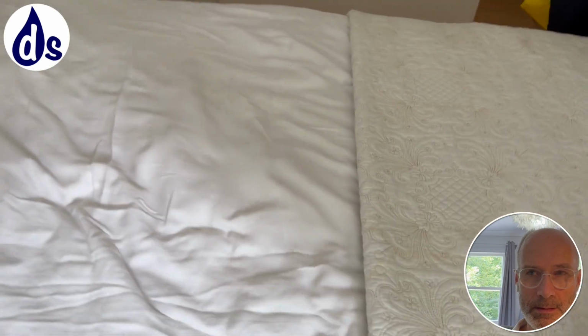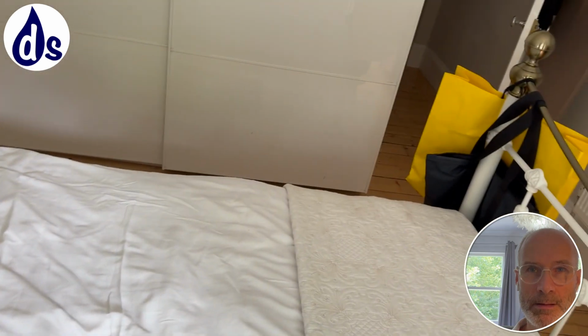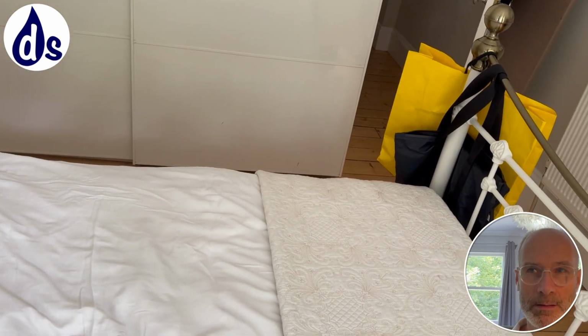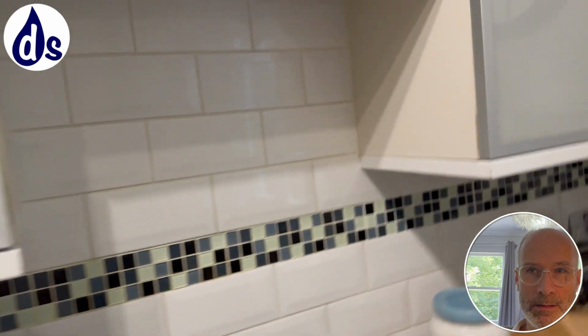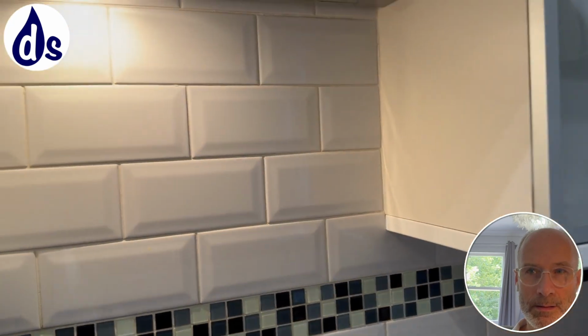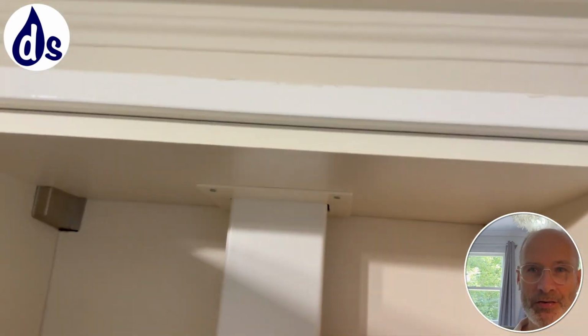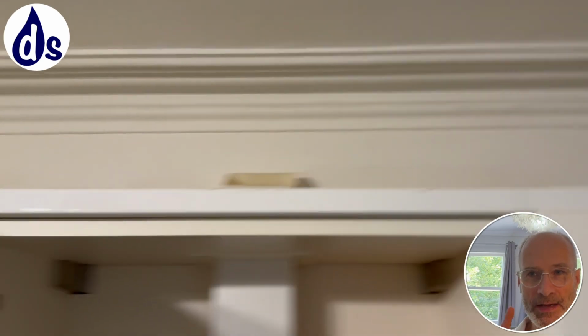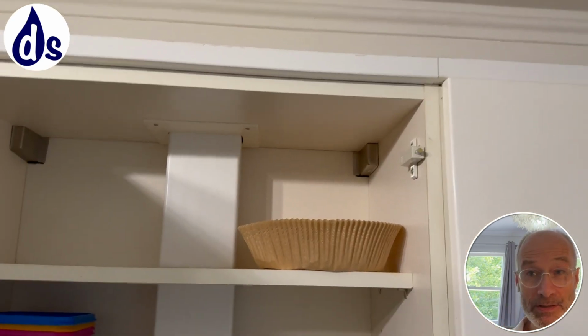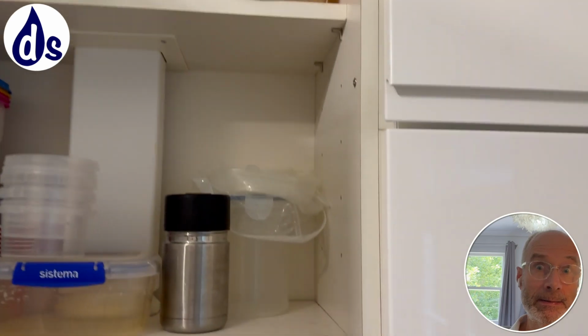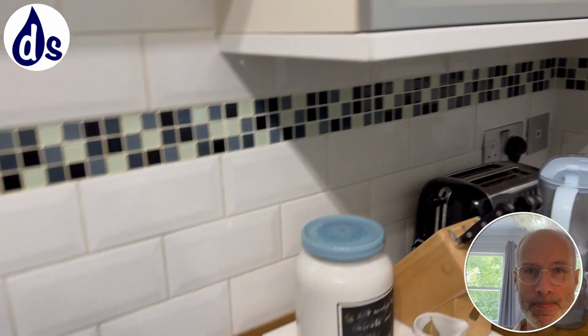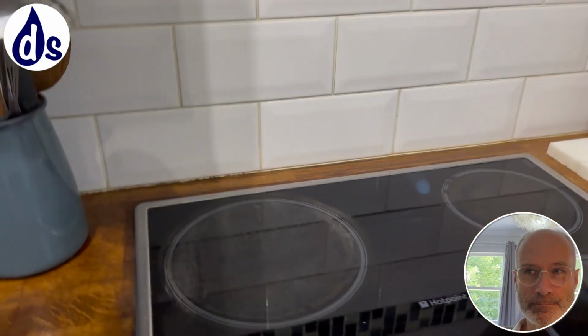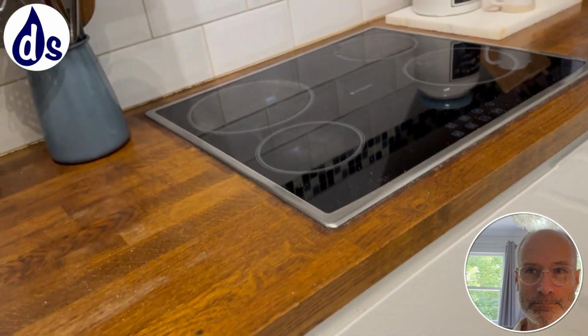So I'm going to measure the airflow from the bathroom with an air monitor. The kitchen extractor fan doesn't go out. When you pull this out, it's very common in the UK for kitchen extractor fans not to be externally ducted. Since 2012, it was a building regulations requirement, but unfortunately people don't follow it and no one checks. So any vapor from cooking is going to diffuse around the rest of the house, and obviously drying clothes internally. So use a dehumidifier for that.